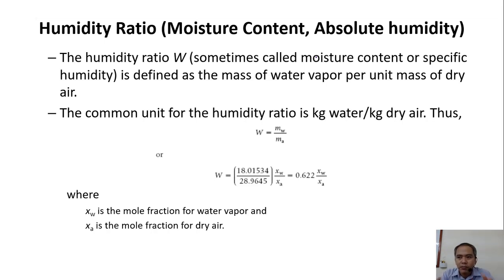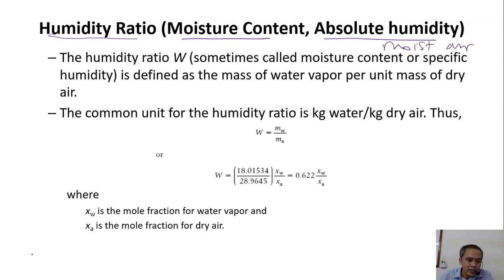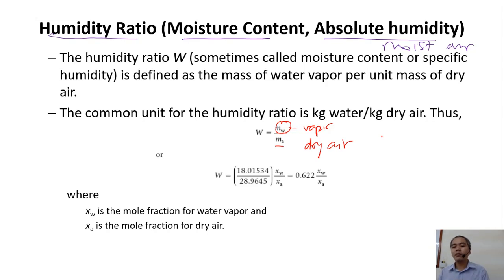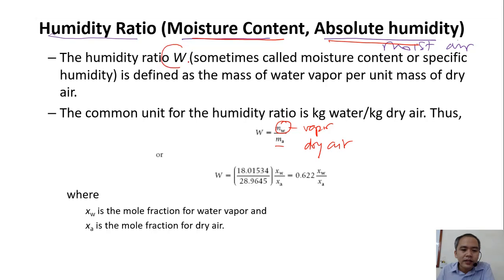We go to a very important parameter of moist air that you need to know. That's humidity ratio, or people call it moisture content, or absolute humidity of the moist air. This is the amount of vapor divided by the amount of dry air — how many kilograms of vapor per kilogram of dry air. That is called absolute humidity, or humidity ratio, or moisture content. The indicator is W: mass of water vapor per unit mass of dry air.